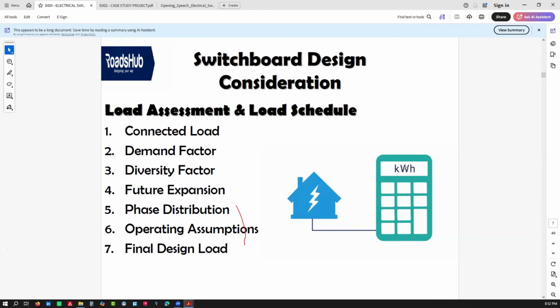Every load change is recorded for future assessment and improvement of the system. So load assessment is one of the design considerations when we design these switchboards, because these are the centralized point to which power will come and be supplied. You have a main breaker, outgoing breakers, and then you have loads. If you do proper sizing and proper load scheduling, you make sure your system does not have an issue. This is one of the things that corrupts a better system if you do it wrong.